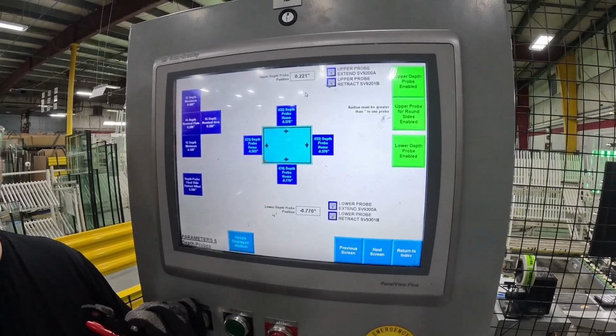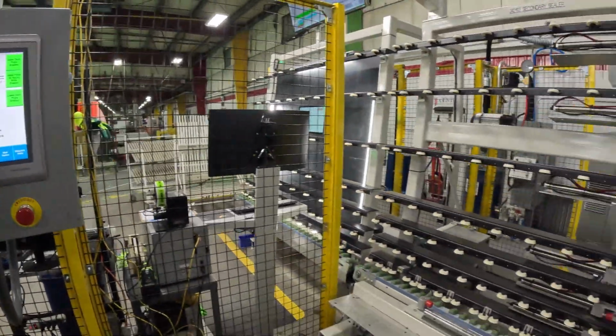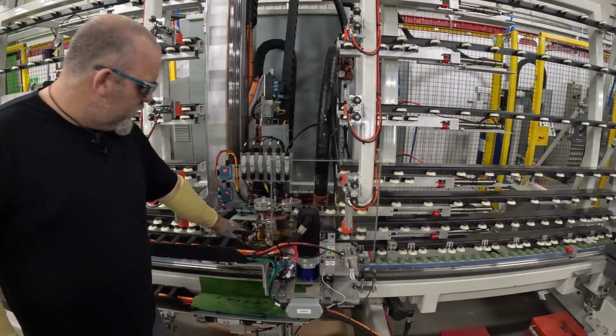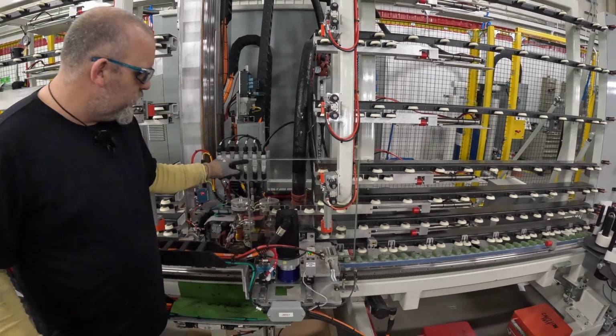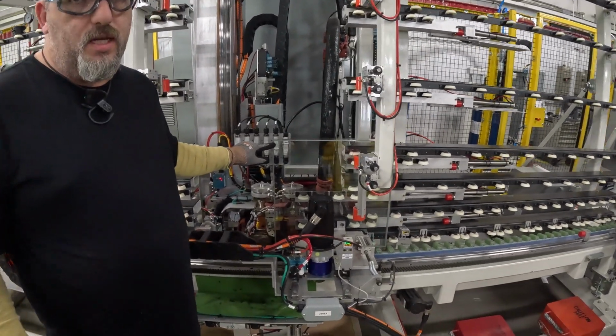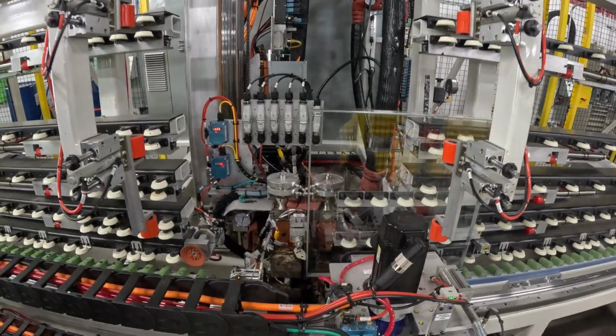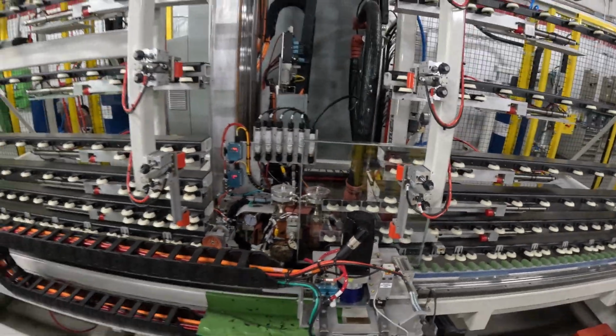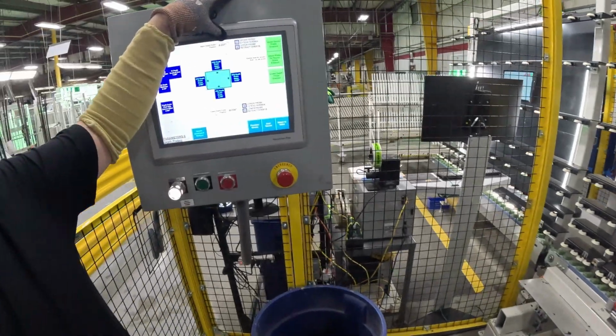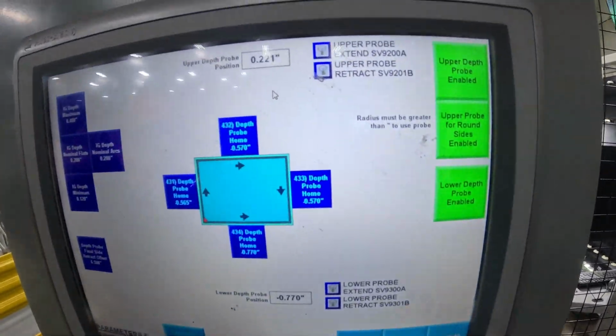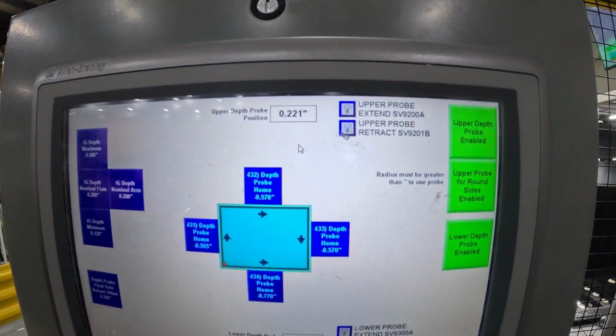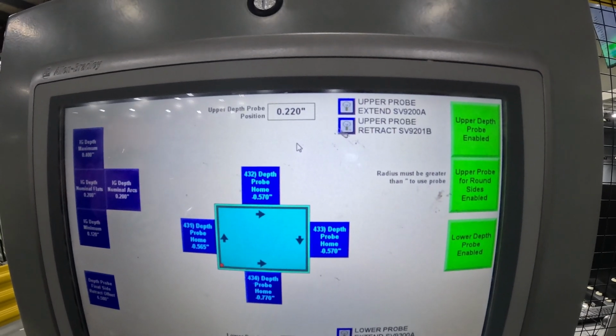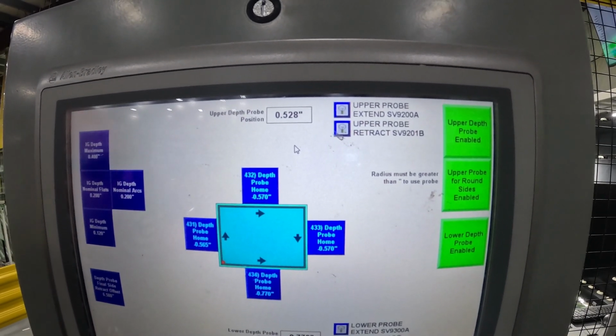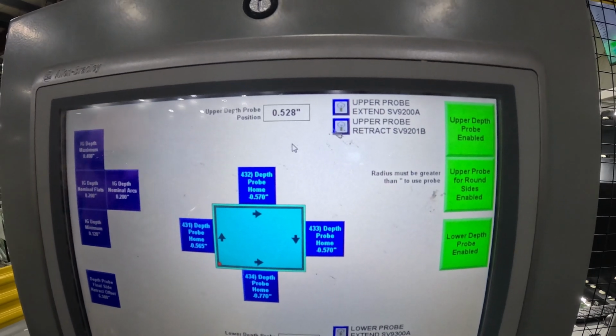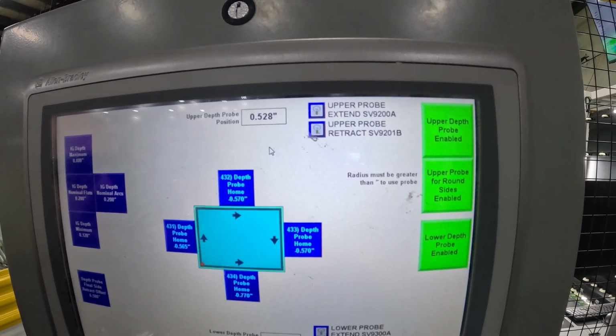Now, once the next step I hit, the head is going to go up the unit, and this will measure along that all the way to the top, right? So what you want to watch is this number here as it trends up the unit. So we're at 220, and it might change a little bit as it goes up the unit. So when I hit start, see how it went to about 230 as soon as it started moving? So that's still within tolerance.